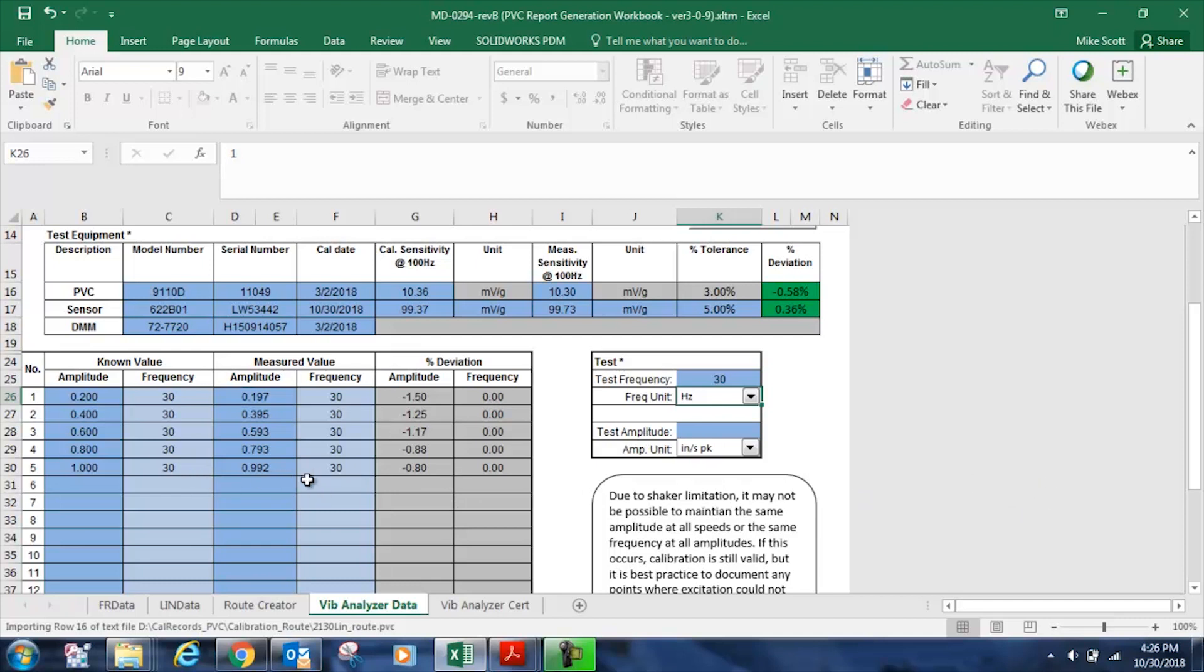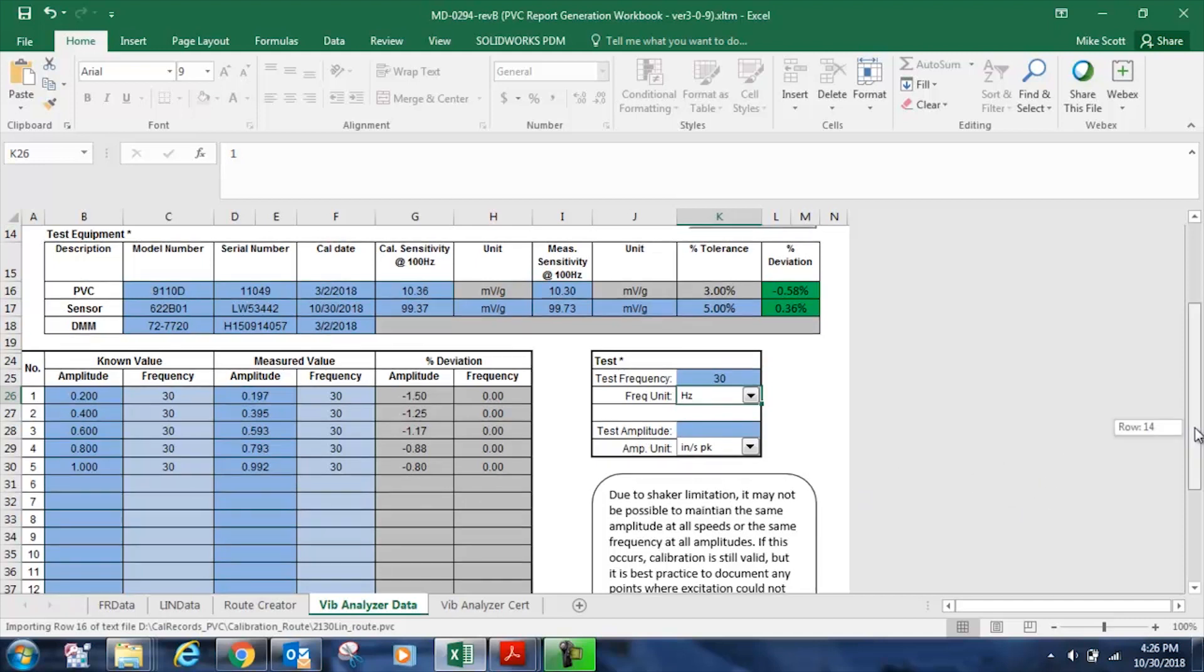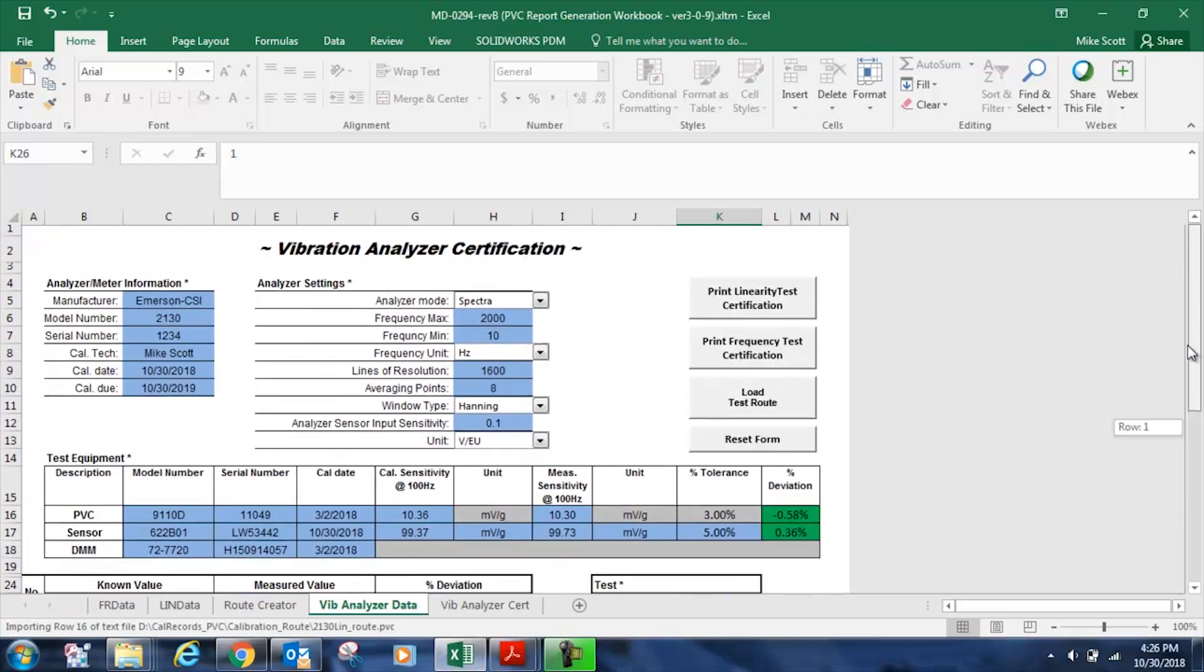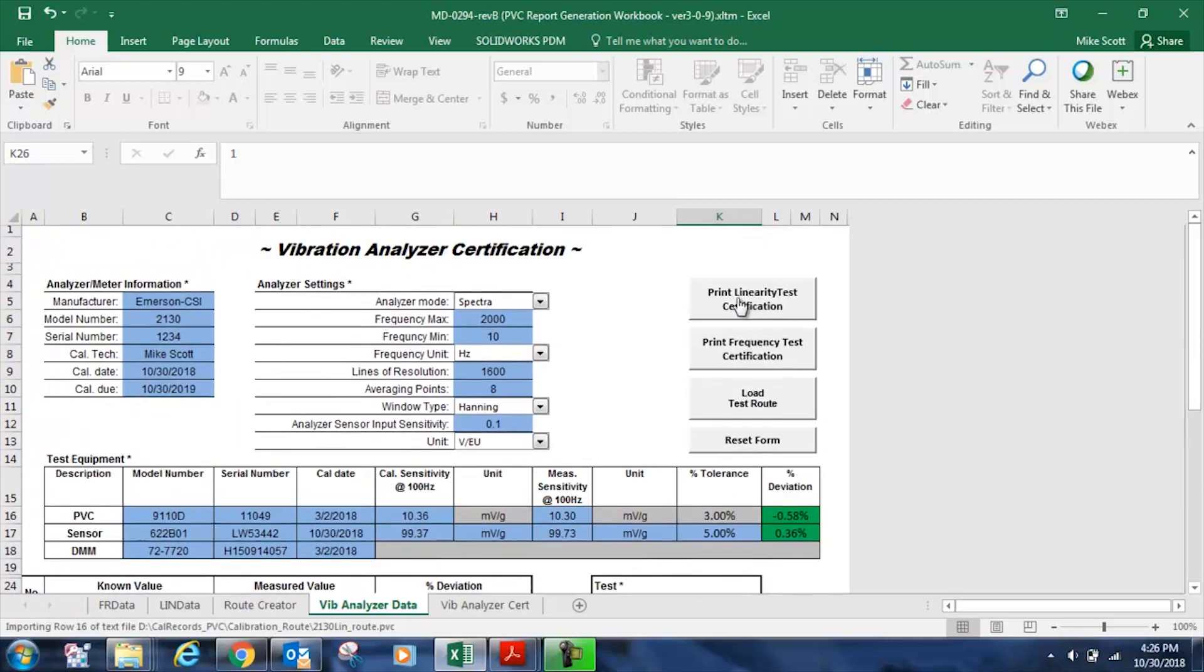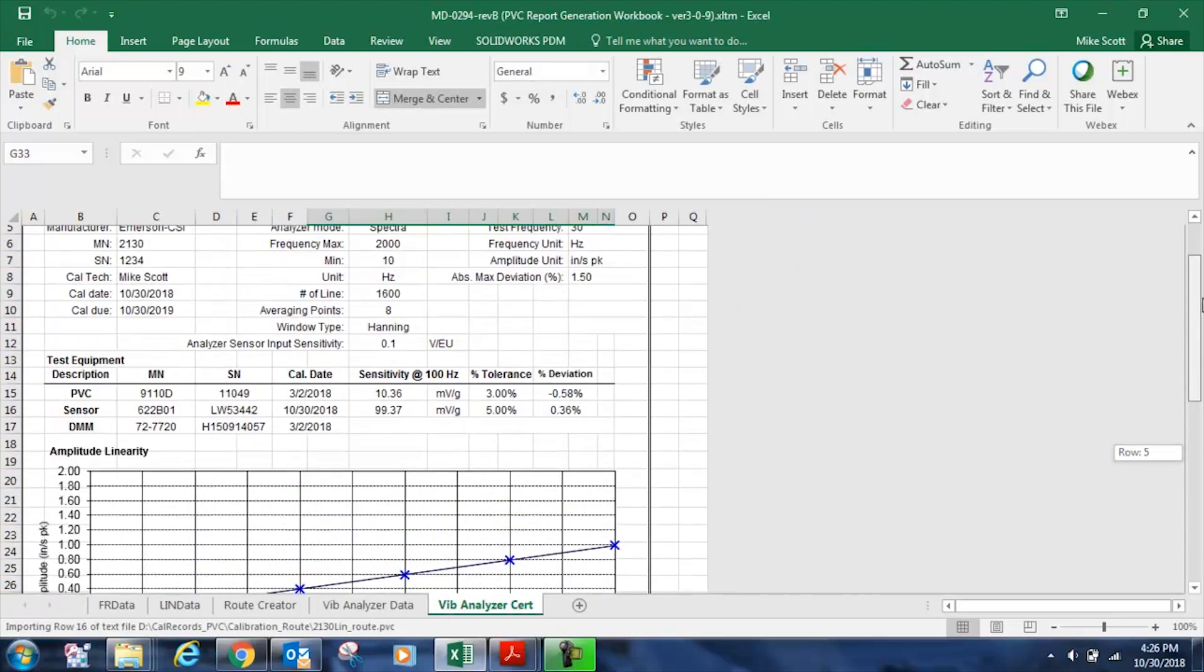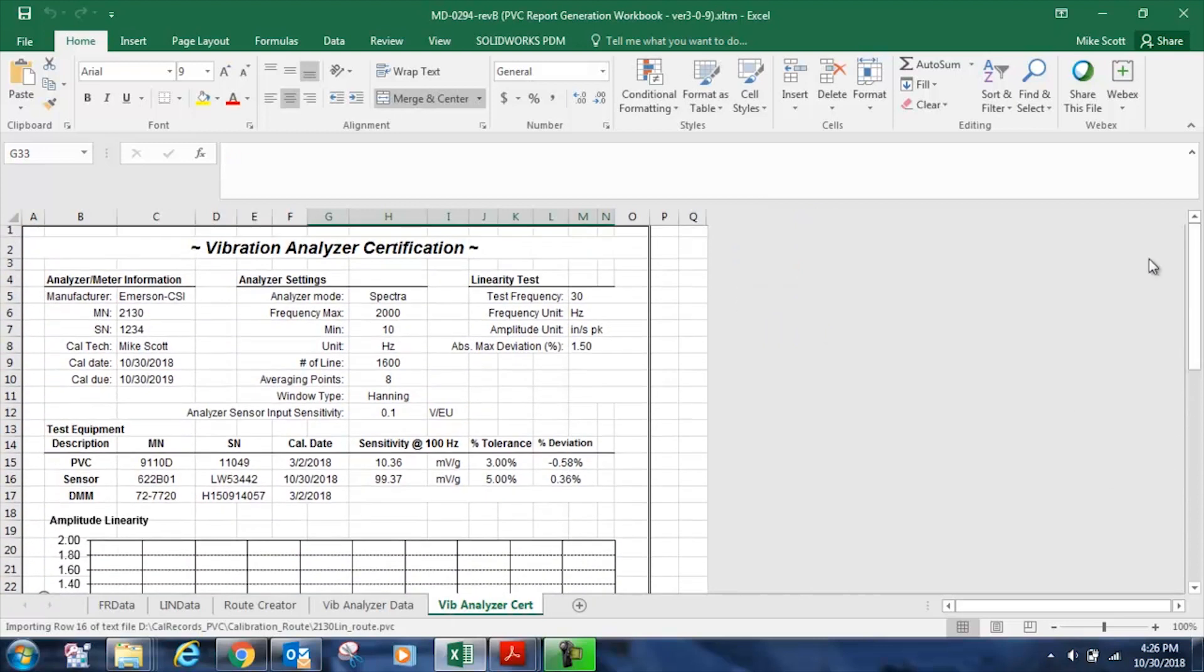Now that all that data is entered, we can create the linearity certificate simply by pressing print linearity certification. And you can see that I have a vibration analyzer certification that I can print or save as a PDF. And it's NIST traceable, which is noted at the bottom. I'll show you in a moment.